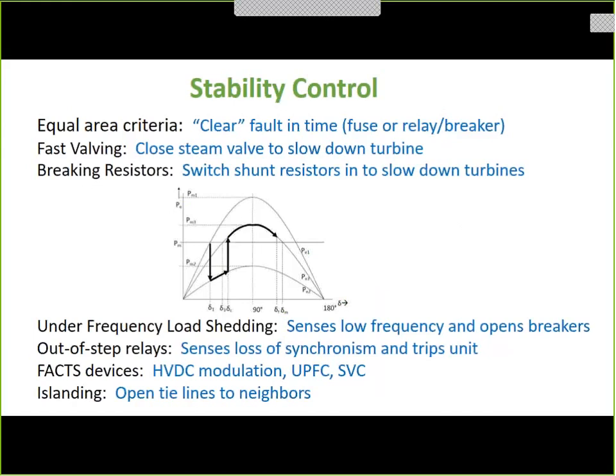It's kind of fun. We have a thing called equal area criteria, which on this diagram says that if you're operating at this line called PM and you have a short, it lowers the voltage and that lowers the power output down to this bottom curve, which has a maximum of PM2. And then you want to clear it. You want to get rid of that short circuit, but you're going to only come back up to this line, PM1. The answer is the area over here has to be bigger than or equal to the area here.